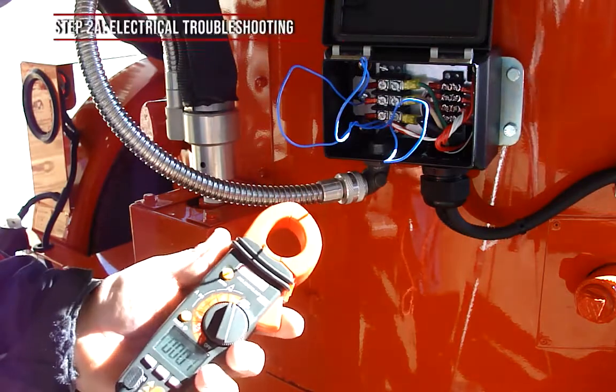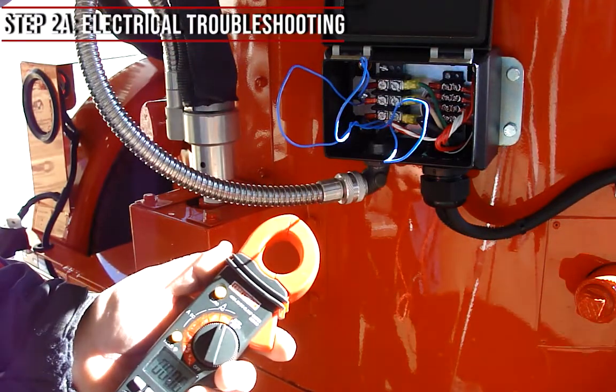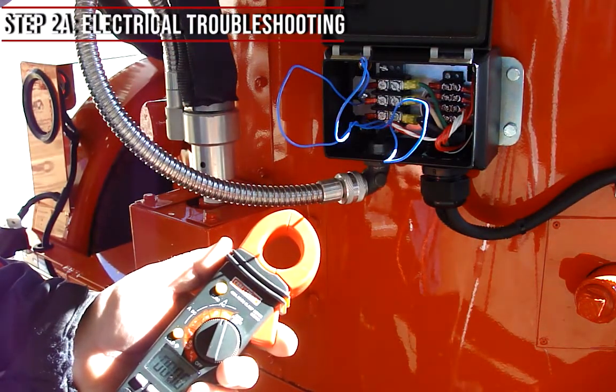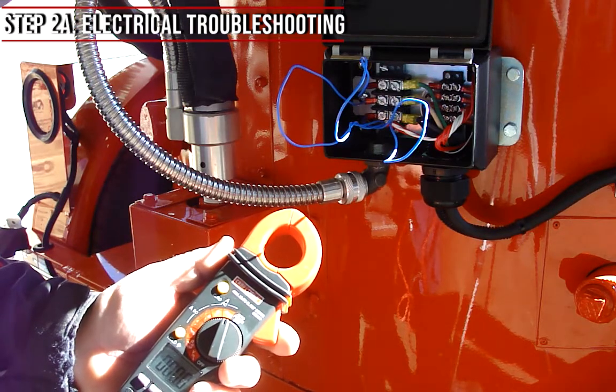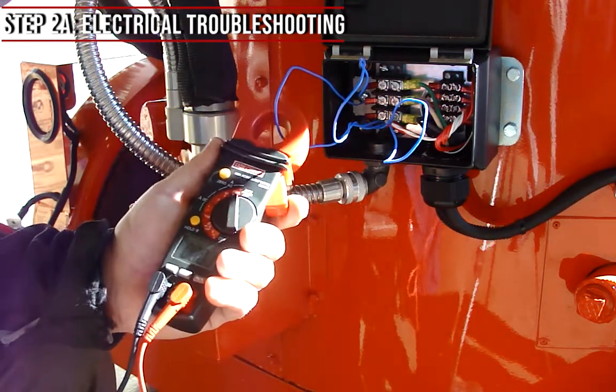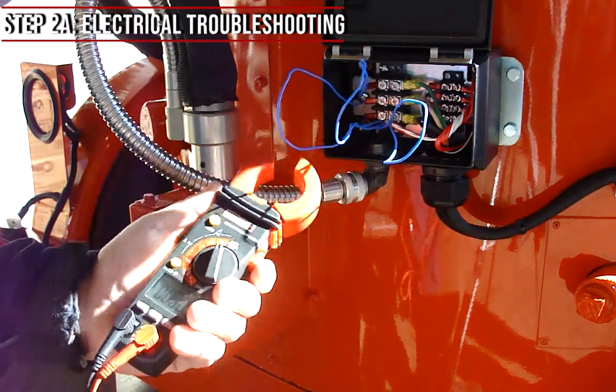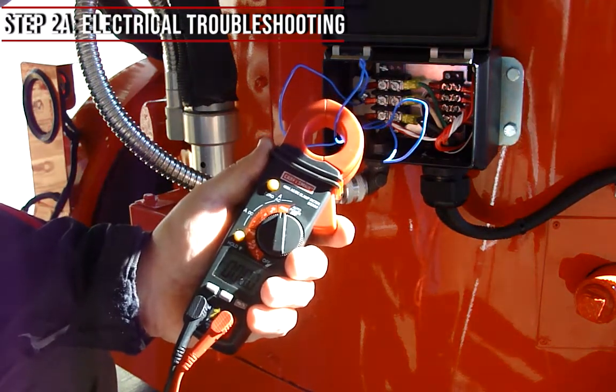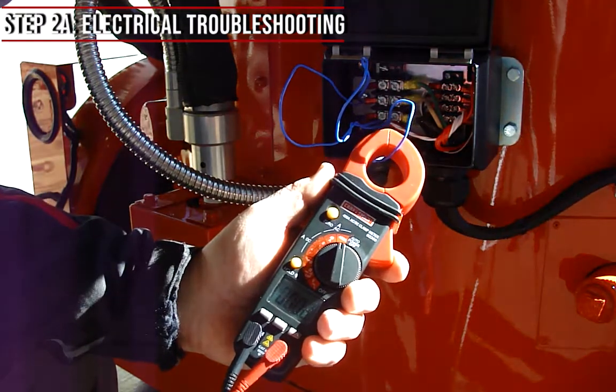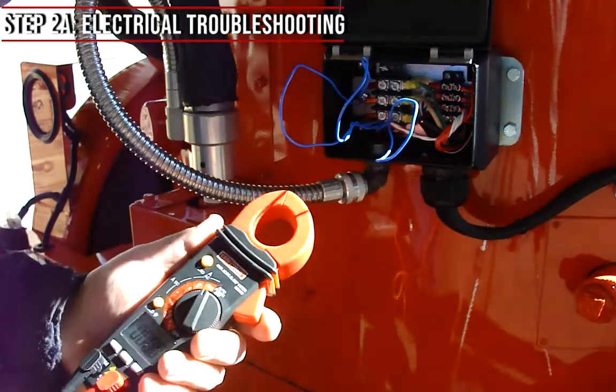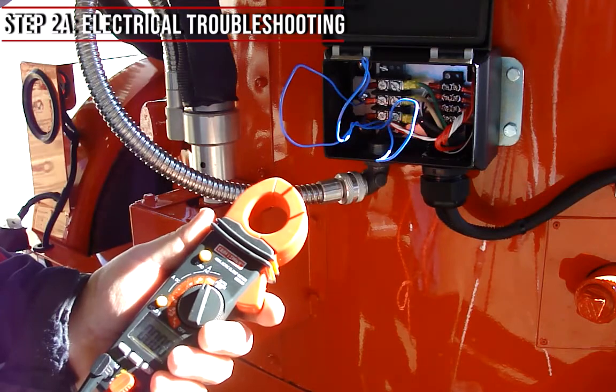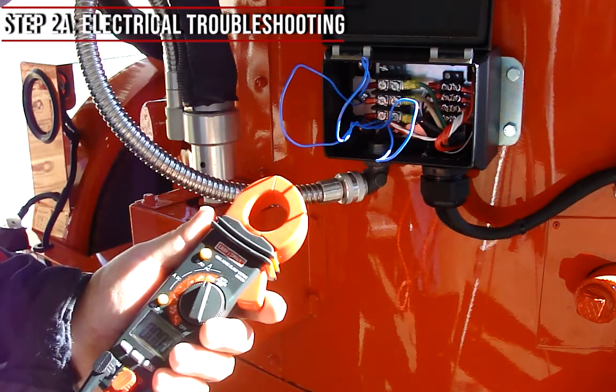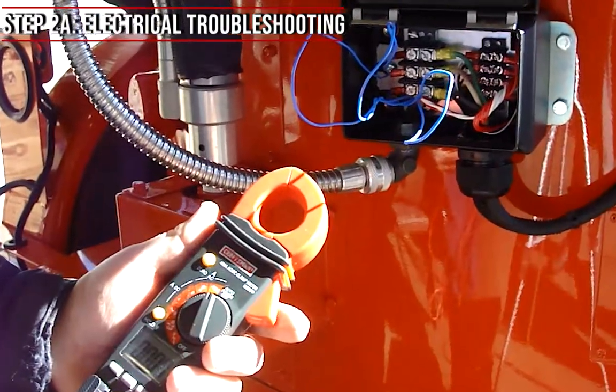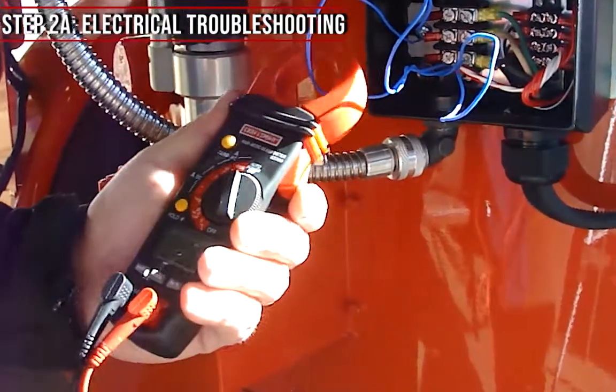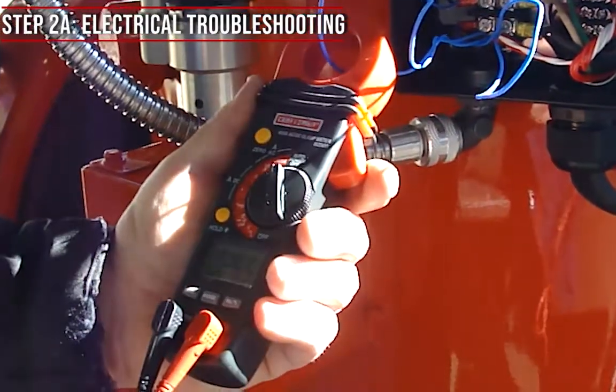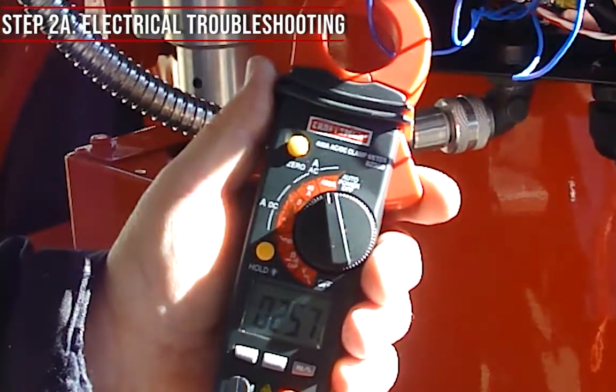Step 2A of electrical troubleshooting is to check the 3 heating element wires, the blue wires, inside of the junction box. Always use a clamp-on meter to perform this test. Each wire should have the same amp reading, plus or minus 1 amp. If the machine is cold, proper amperage should be between 30 and 35 amps. If the machine is hot, proper amperage should be 20 to 22 amps. If yes, you have proper amperage, the hose should be working properly. If no, go on to step 3 of electrical troubleshooting.